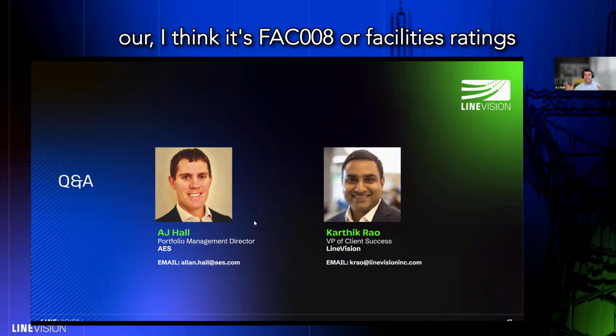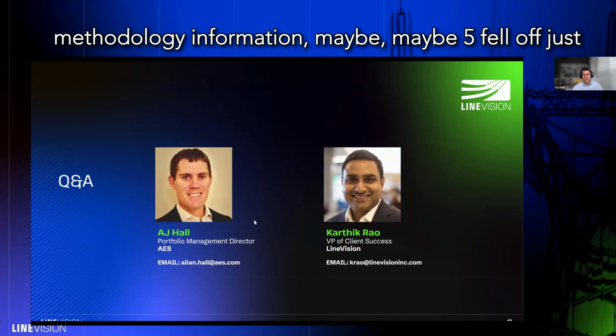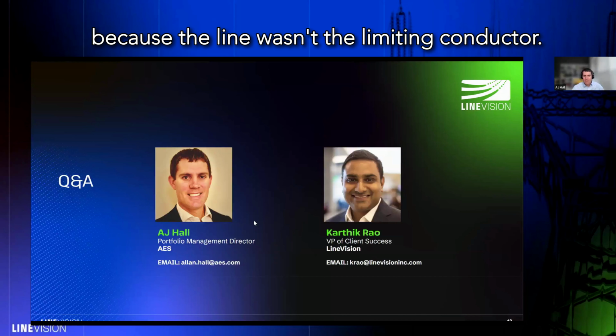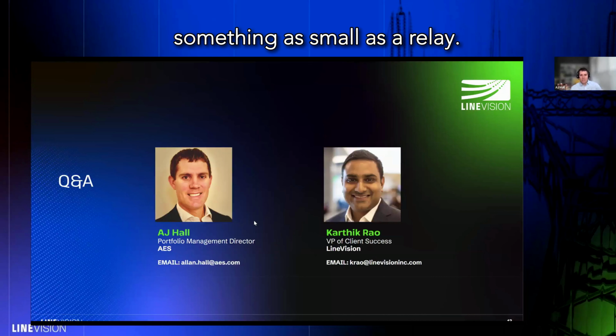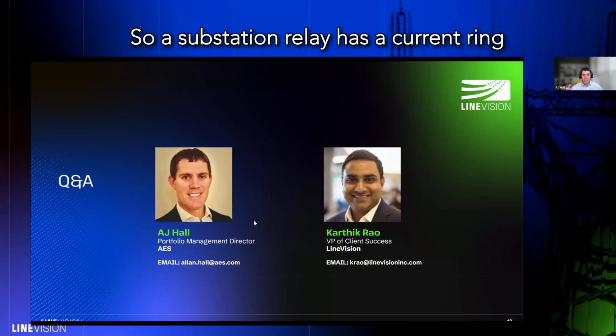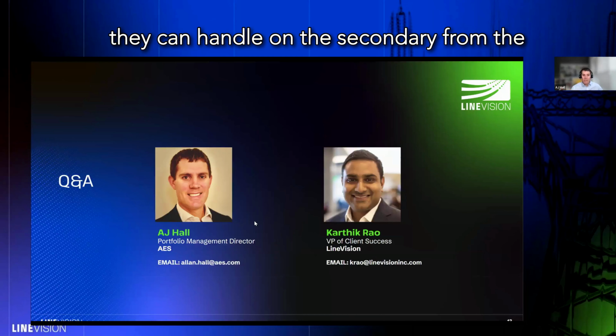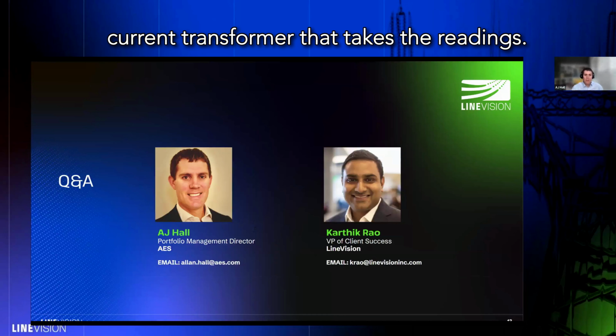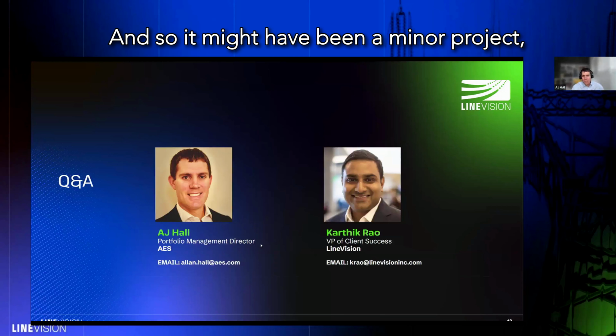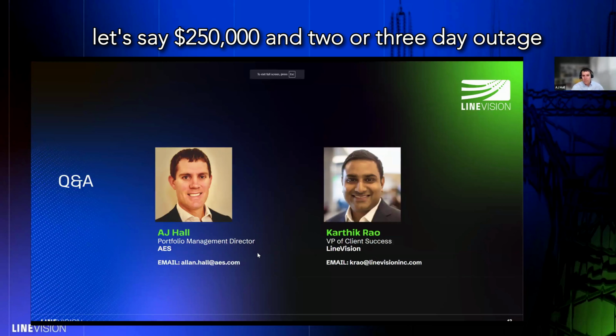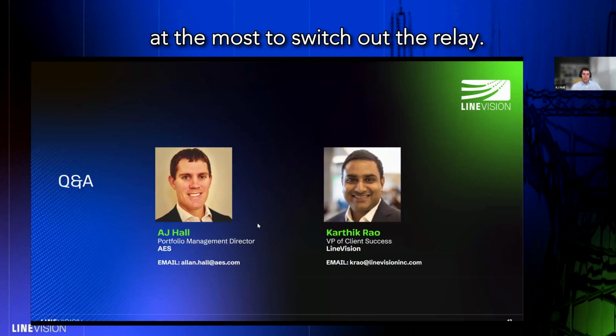I think it's FAC 008, facilities ratings methodology information. Maybe 5 fell off just because the line wasn't the limiting conductor. There might have been something as small as a relay. A substation relay has a current rating it can handle on the secondary from the current transformer that takes the readings. So it might have been a minor project, let's say $250,000 and a 2 or 3 day outage at most to switch out the relay.